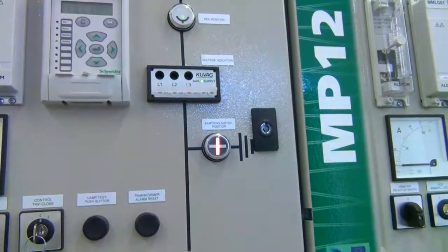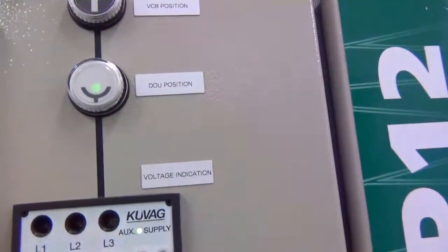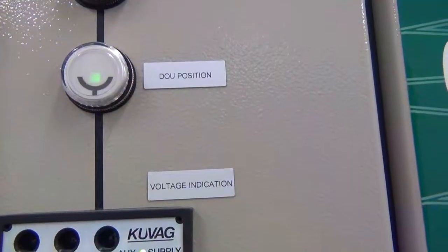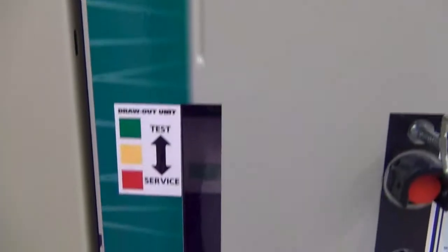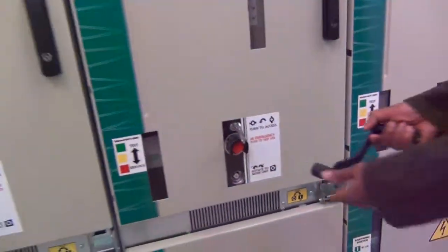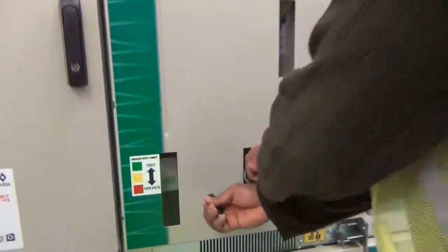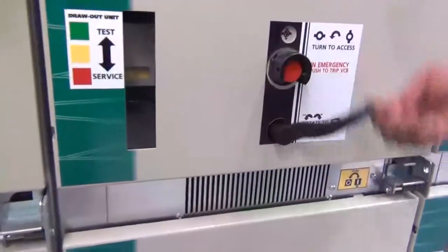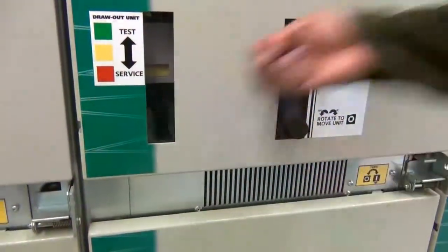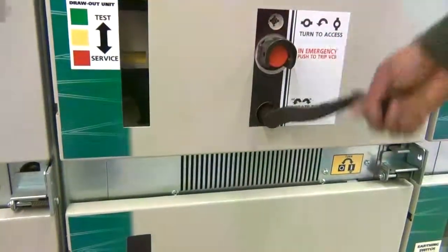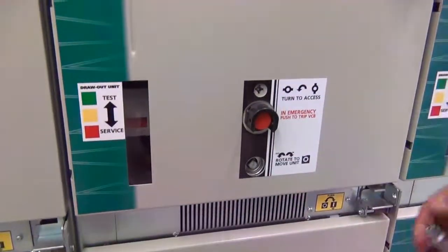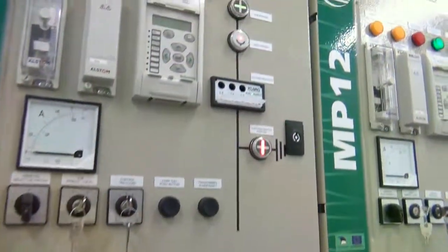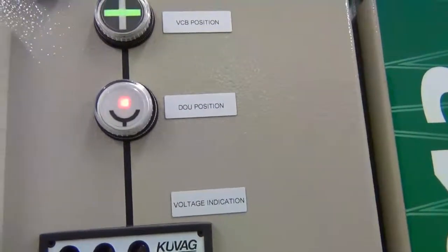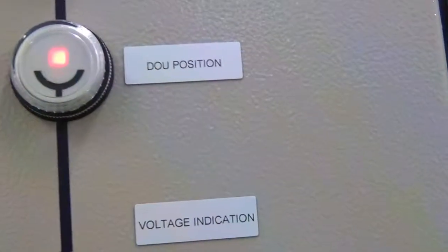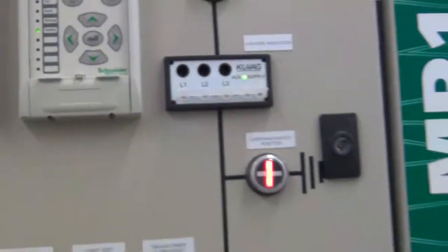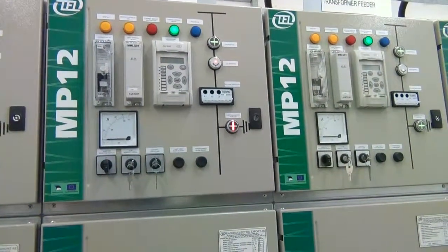Now we will put the draw-out unit inside the breaker. As you can see, the draw-out position of the breaker is indicated here. It is green, it is in test condition, and the same can be seen here. Now the breaker will be racked in. You can see the status of the indication as the rollers. It is now in the intermediate condition, and finally it will turn red in the service condition. So now the breaker is ready to be put on and off. The draw-out unit is also clearly shown here. It has turned red. Okay, and now the breaker is in service condition, ready to be closed and open.